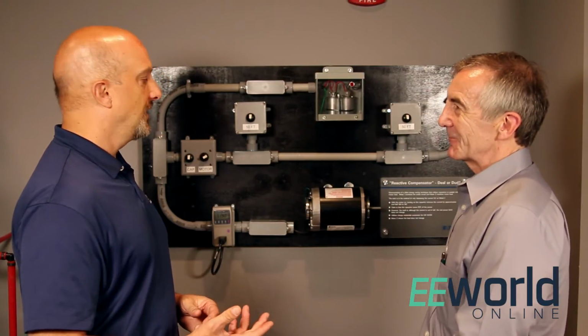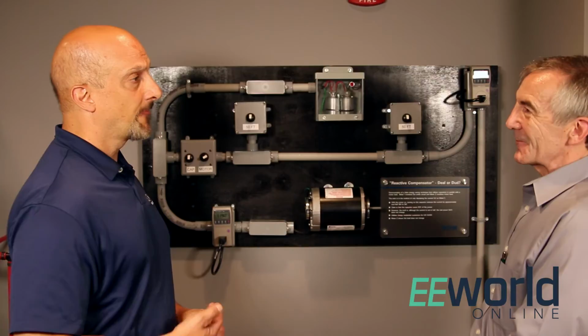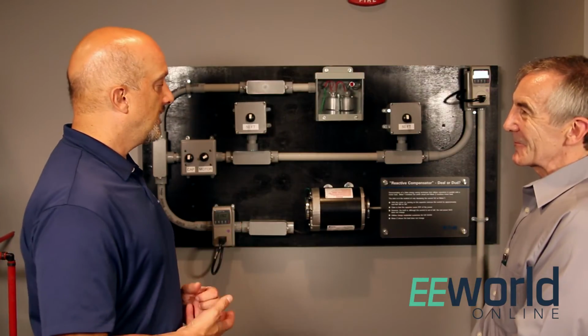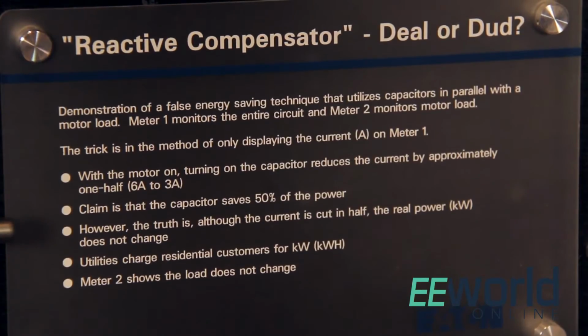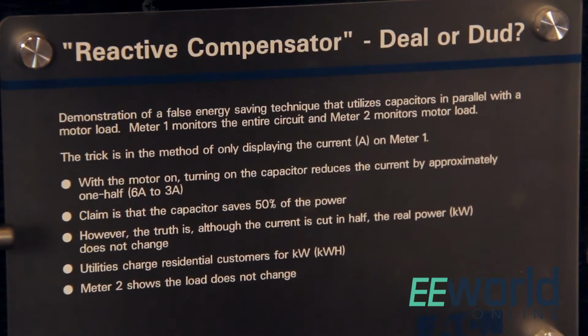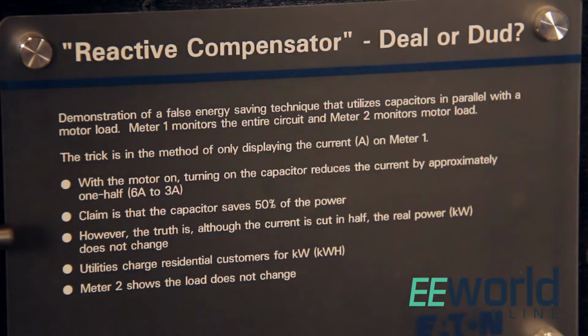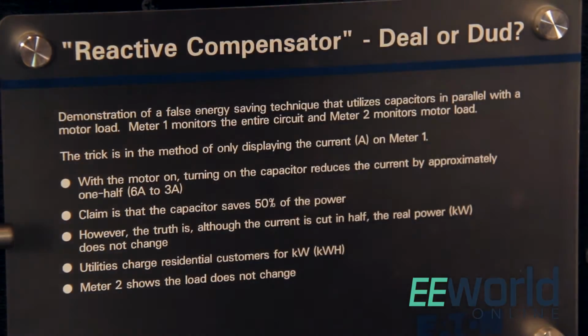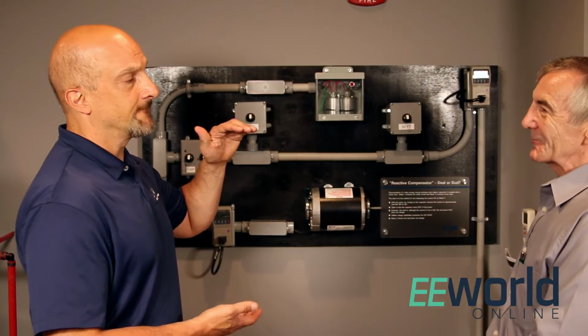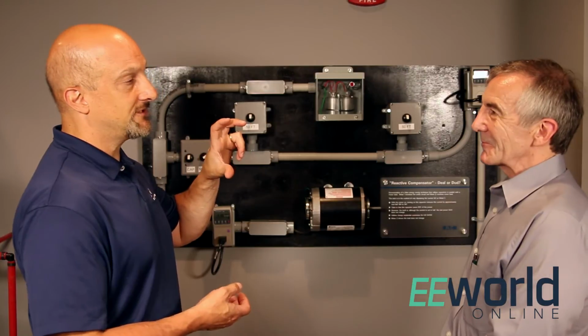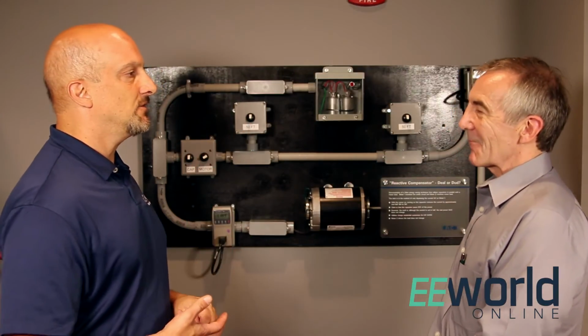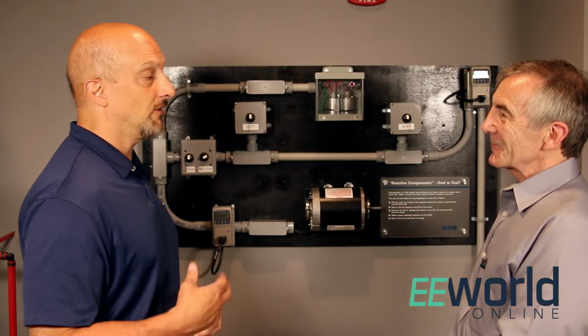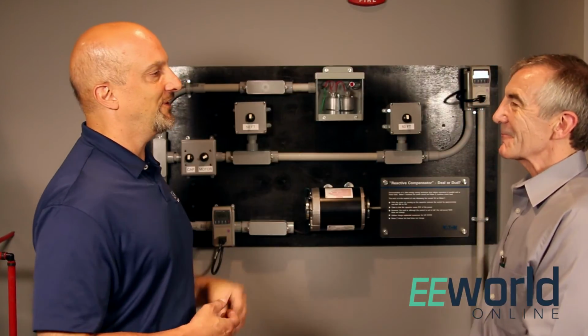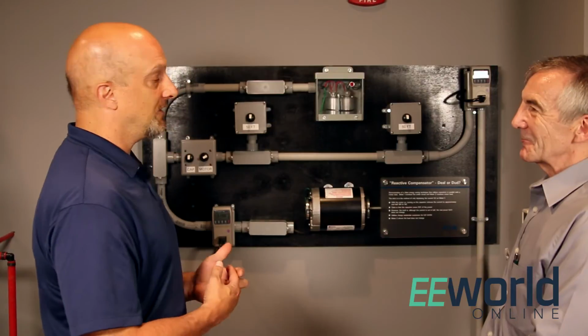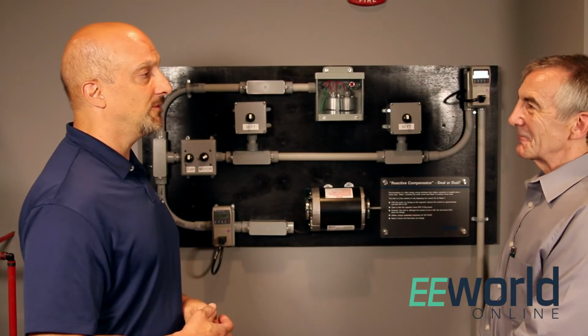And what a power factor penalty is, again, like you said, with commercial or industrial customers, the utility bills them on a rate that's basically the kilowatts plus, if you are using a lot of reactive power, and of course a lot of industrials especially use a lot of motors, and in commercial buildings they use a lot of HVAC units and a lot of motors. So they want to make sure that their kVA capacity, which is transformer capacity, cable capacity, which is in amps, all of those things are optimized. So if a utility bills a customer that's an industrial or a commercial customer, it's because you're using up the capacity of the system. Thus the word capacitor comes in and takes some of that capacity back and gives it back to the customer, so the utility doesn't have to put a bigger transformer, for example.